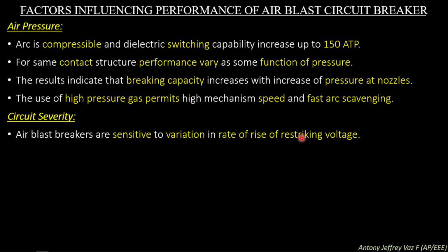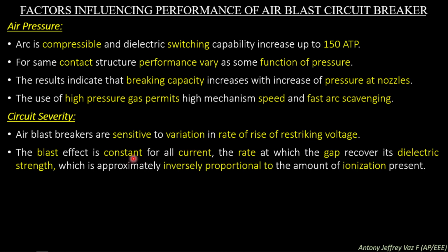The sensitive variation in the compressed air blown can modify the rate of restriking voltage. The blast effect is constant for all current. The rate at which the gap recovers its dielectric strength is approximately inversely proportional to the amount of ionization present.